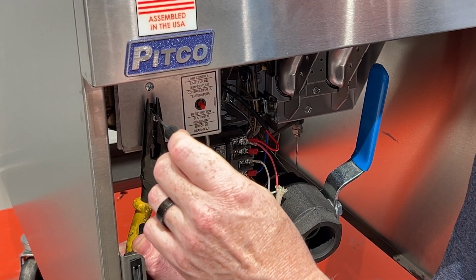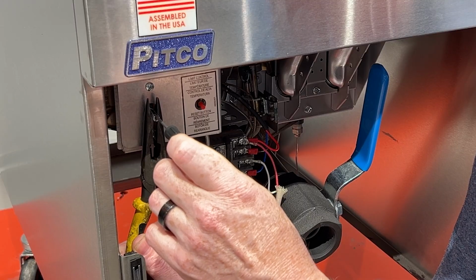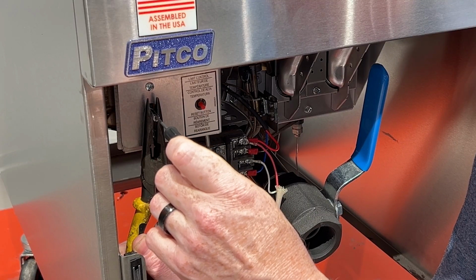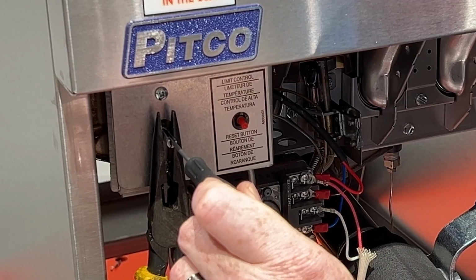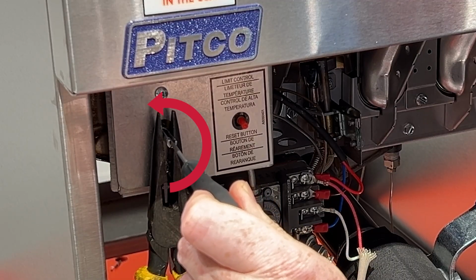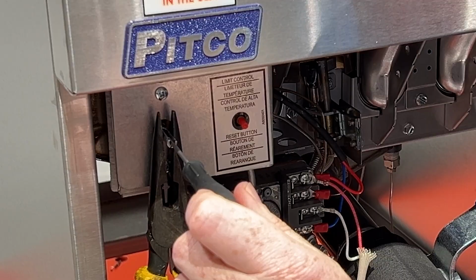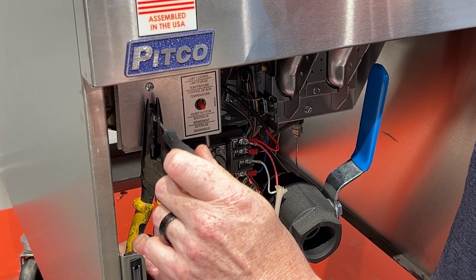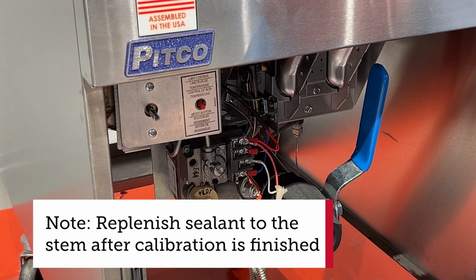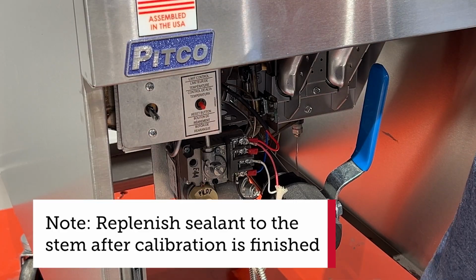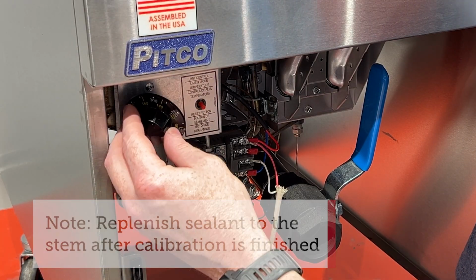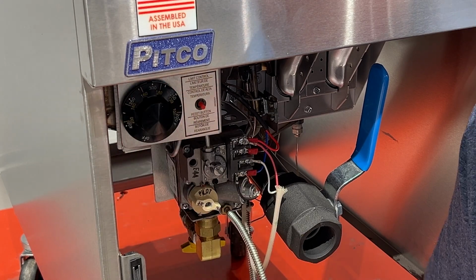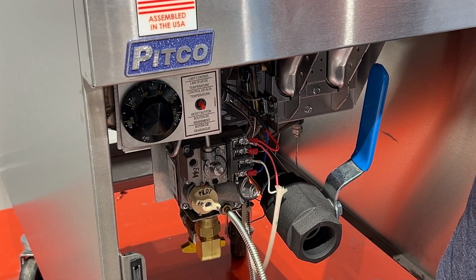Because this thermostat is currently electrically open, I'm going to turn it counterclockwise until it closes, which means we should be at the correct temperature. After making that adjustment, I'll put the knob back on and take the temperature of the oil again to see if any further adjustments are needed.